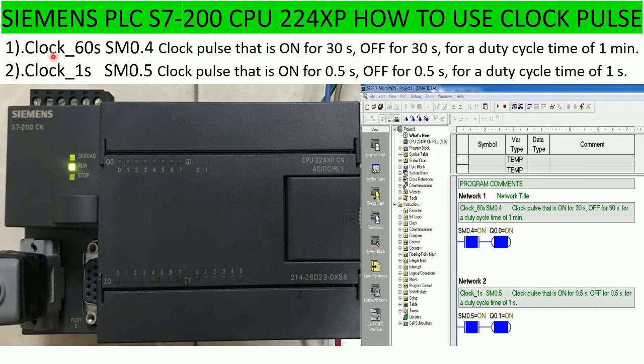So first, when we use SM0.4 clock pulse memory, it means that it will turn on 30 seconds and then turn off 30 seconds, for a duty cycle time of 1 minute.